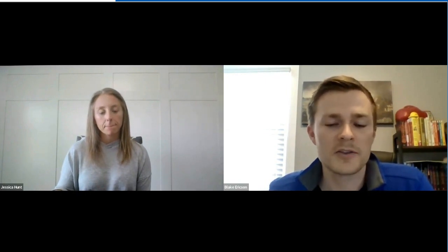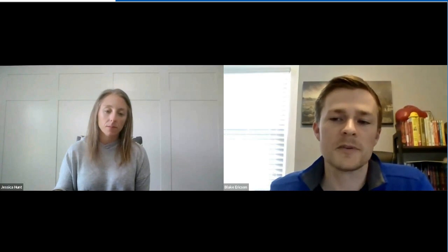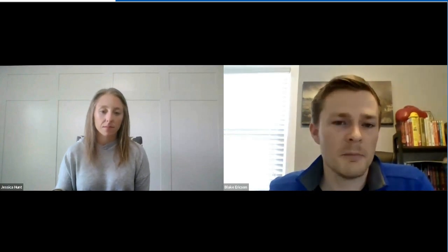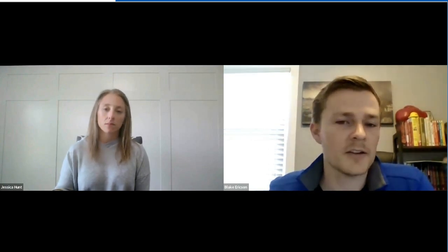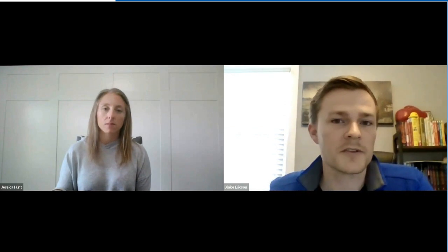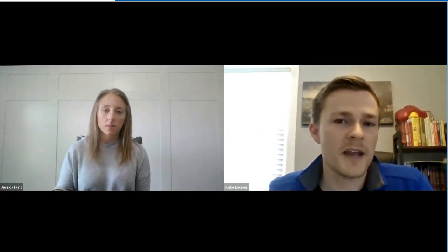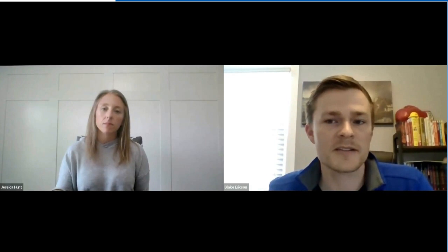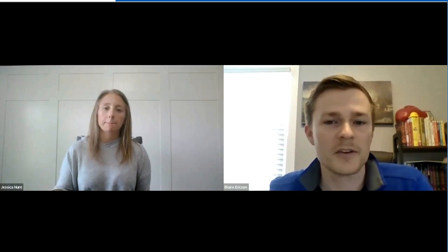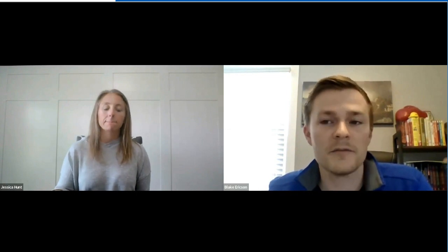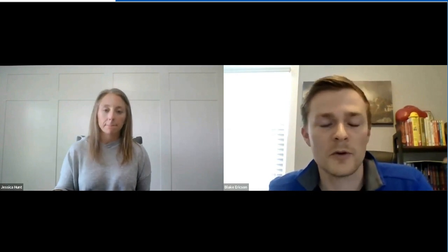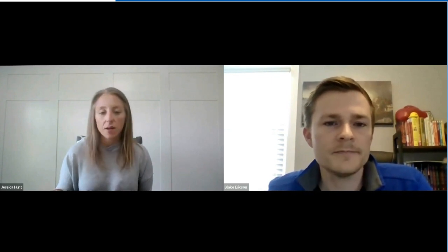So when I mentioned it before, let's just pretend you had a 100 PPM bottle and you were reading 80 or so. So you know that you're 20% low. Well, you shouldn't span it down to match it, because it's very likely that you have some other deeper issues going on. And so it's our recommendation that your span factor should not be touched. But if you must, it should be no greater or less than 5%.